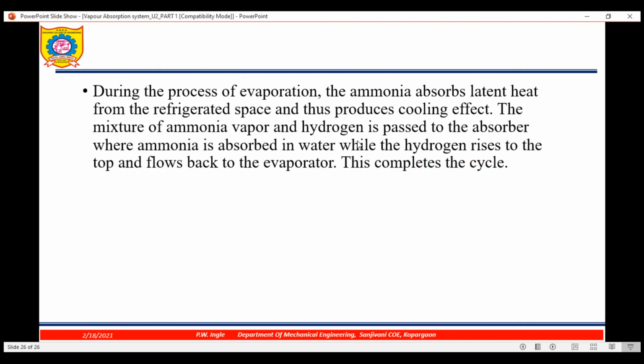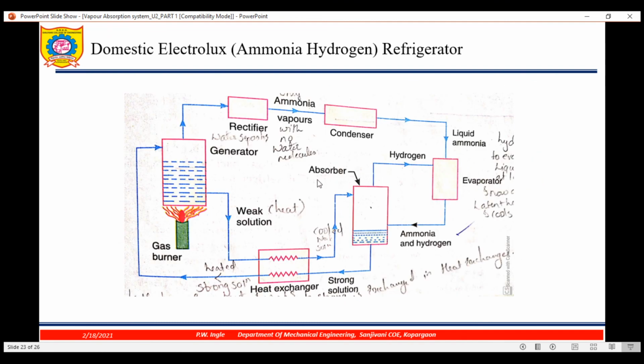The mixture of ammonia vapor and hydrogen is passed to the absorber, where ammonia is absorbed in water while hydrogen rises to the top and flows back to the evaporator, and this completes the cycle. So in short, there are three fluids. The first one is ammonia, used as a refrigerant. Next is hydrogen, which is used to increase the rate of evaporation. And number three is water, which acts as an absorbent. So this completes the explanation of the domestic Electrolux refrigerator. Thank you.